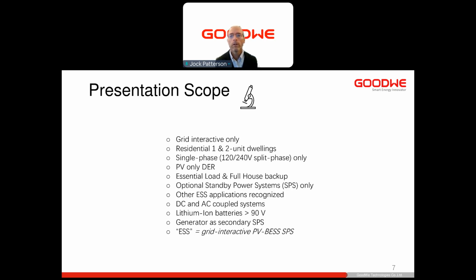Today's scope is ESS, Energy Storage Systems for Residential Use. The ESS abbreviation stands for Grid Interactive PV Battery Energy Storage Standby Power Systems. That's a mouthful, but we're talking about residential systems tied to the grid, split phase, where the only on-site generated power is from PV. With these systems we can provide standby power, which we'll define. This will be power used for either partial backup or full house backup. There will be other ESS applications we can talk about, but our focus will be on backing up power when the grid is lost.